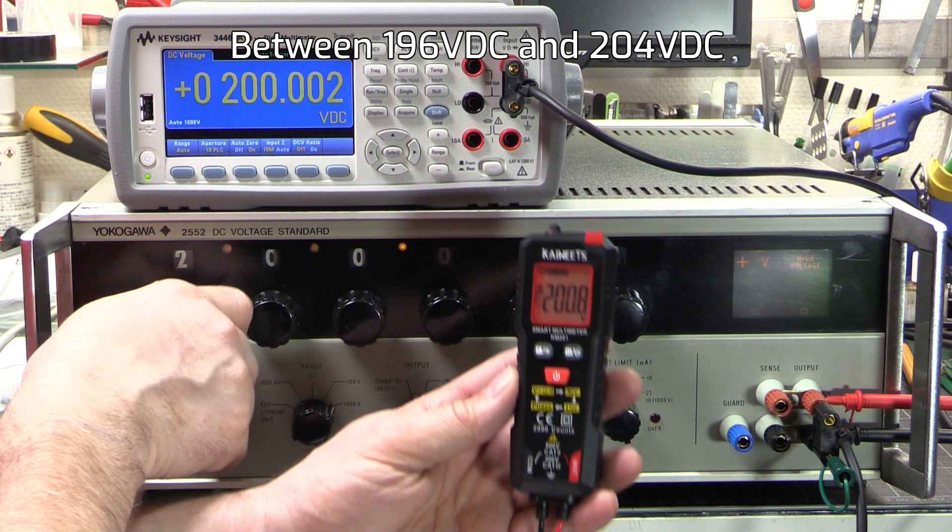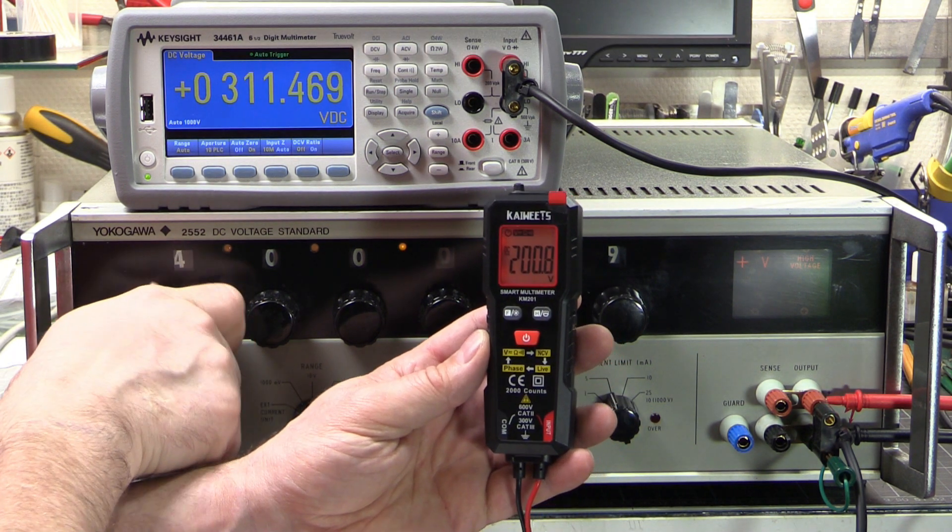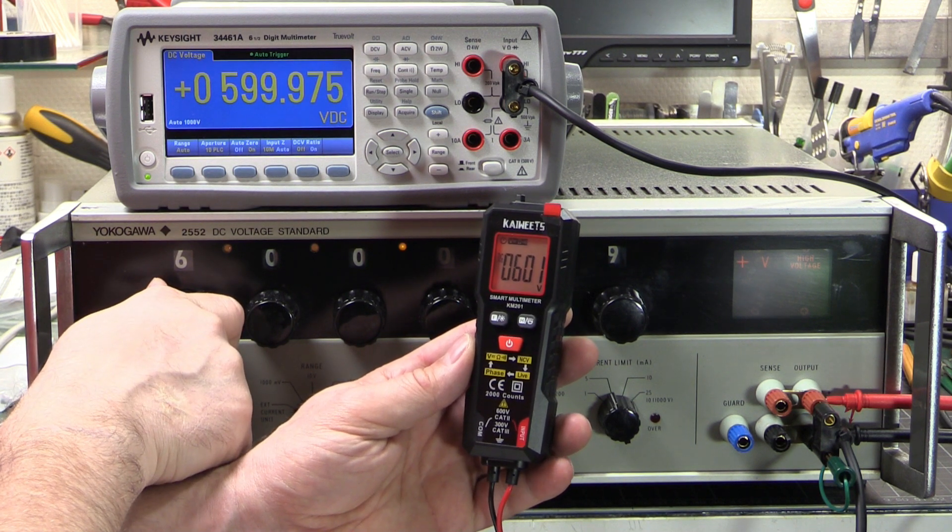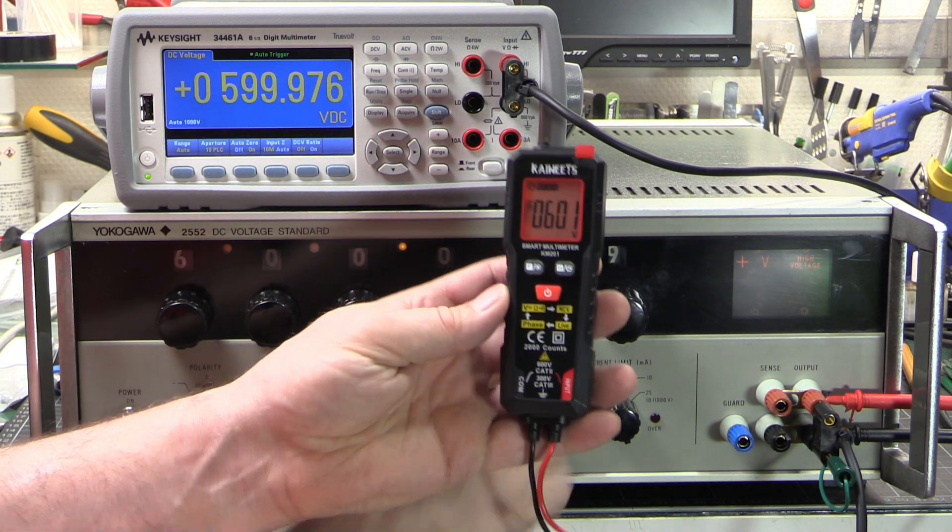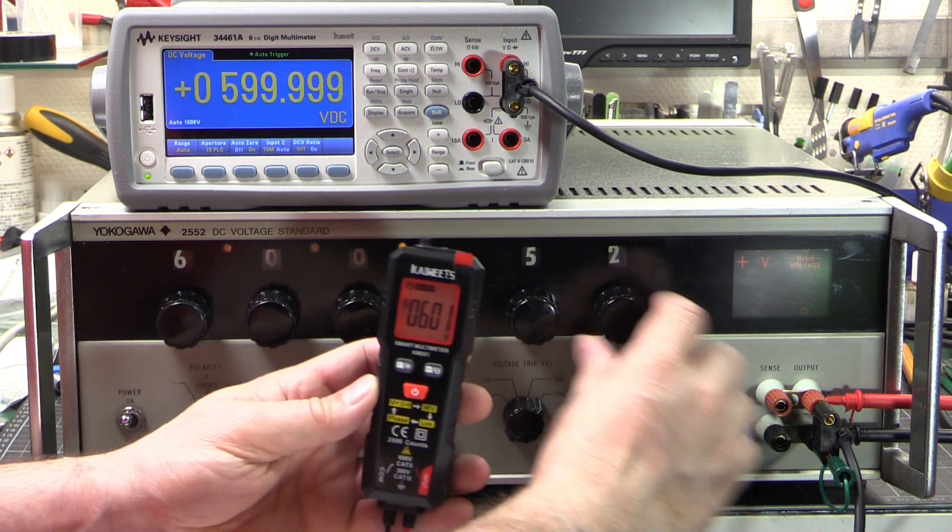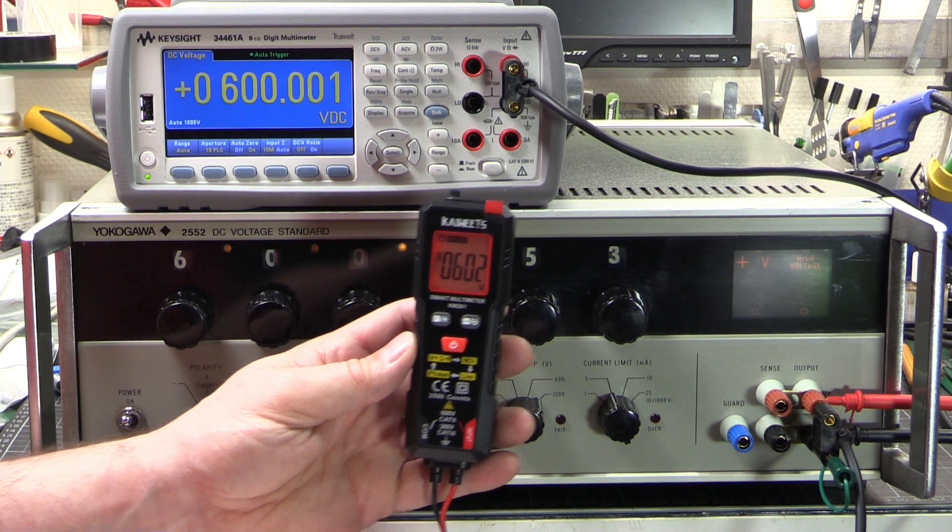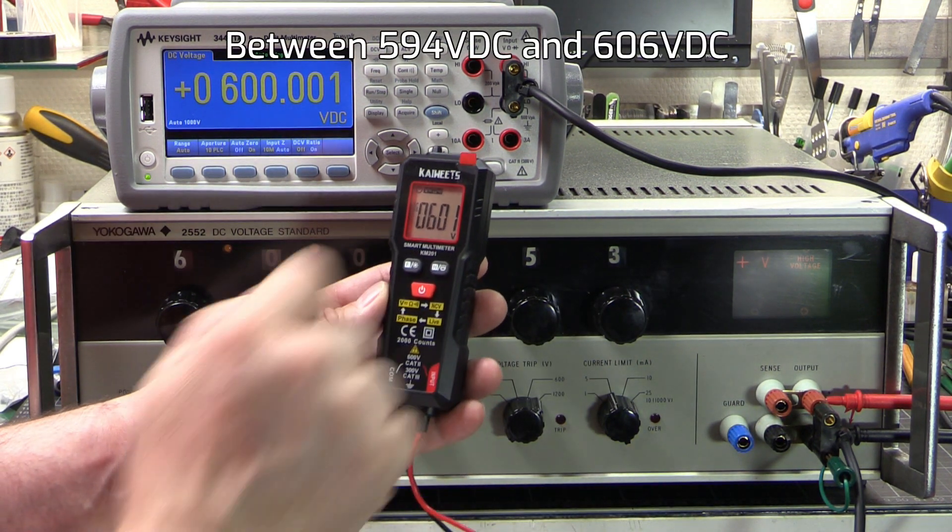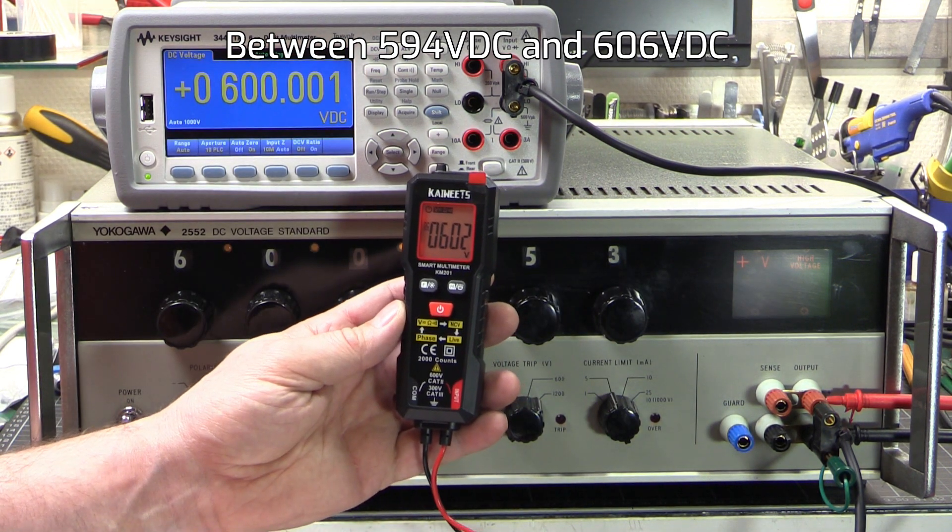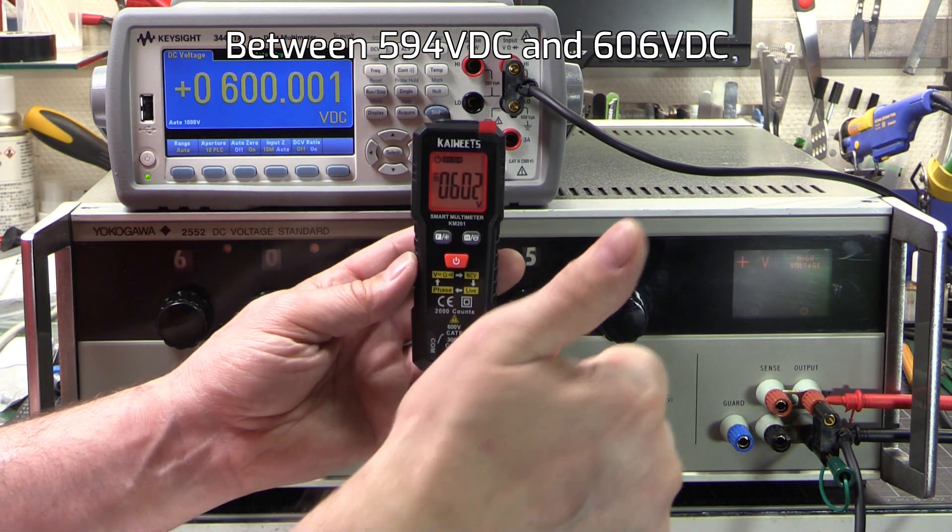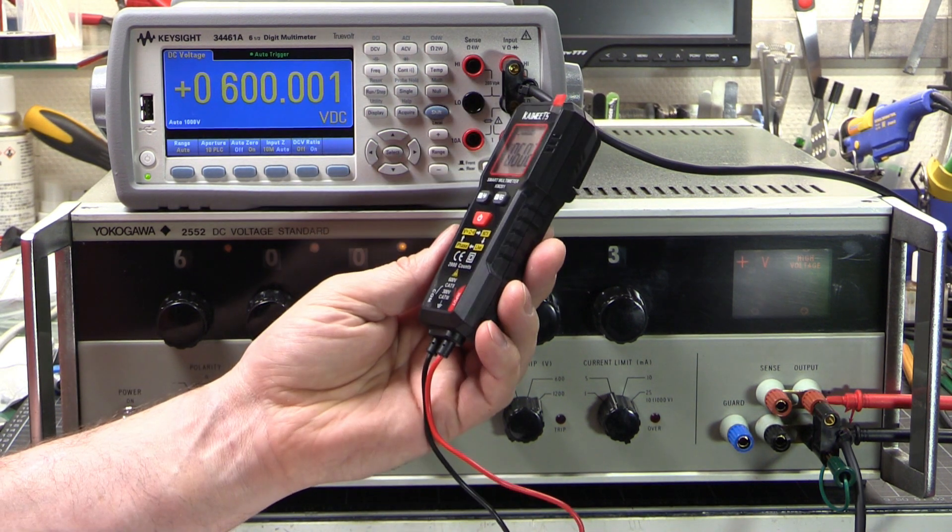And the last one. 600 volts. 500 volts. 600 volts. It's beeping at us. Give this a little bit of a tweak. 600 volts. Give it one more. There we go. And we've got 601 volts for 600.000. Yeah. This thing reads fine. There's nothing wrong with the calibration or the accuracy of this thing. It's, yeah. Thumbs up on that.